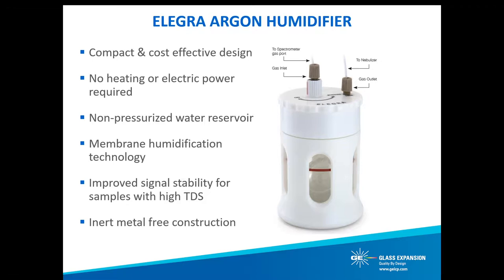The Guardian inline filter protects your nebulizer from blockages due to fibers. But to prevent nebulizer blockages caused by the buildup of salt — for any high total dissolved solids, high salt, or high acid application — an argon humidifier is an essential accessory. Glass Expansion's Elegra is a compact, cost-effective humidifier design that provides approximately 100% relative humidity to slow the buildup of salt at the tip of your nebulizer. We'll cover the performance of the Elegra in much more detail in an upcoming webinar focused more on applications.